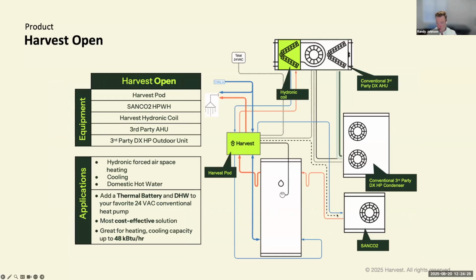We're essentially taking this off-the-shelf heat pump water heater. It's a split system, with a condenser outside, as you can see on the bottom right. We recommend a minimum of 119 gallons of storage on a single family home, because we're using both space heating and domestic hot water with a single storage tank. There are other configurations - an 83 gallon tank sometimes used for multifamily applications with a smaller heating load, or for a bigger home with a larger heating load you can plumb two of those 83 gallon tanks in series to get 166 gallons of thermal storage, essentially a larger thermal battery with a longer runtime.